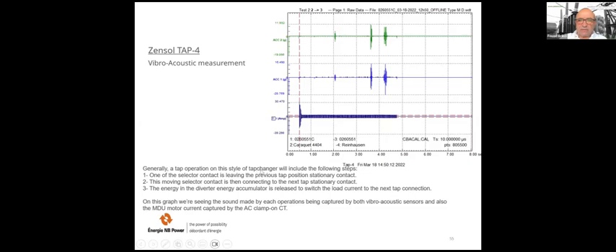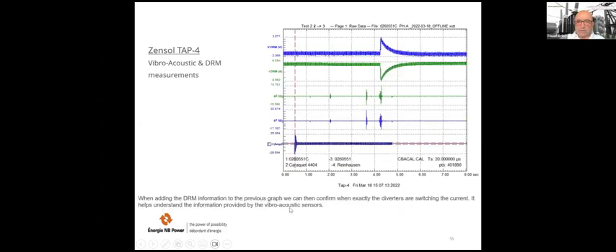Generally, tap operation, this type of tap changer will include the following steps. One of the selector contacts is leaving the previous tap position stationary contact. This moving selector contact is then connecting to the next tap stationary contact. The energy in the diverter energy accumulator is released to switch the load current to the next tap connections. On this graph, we are seeing the sound made by each operation being captured by both vibroacoustic sensors and also the motor current captured by the clamp on the CT.